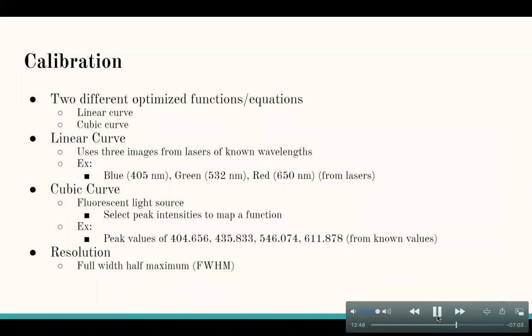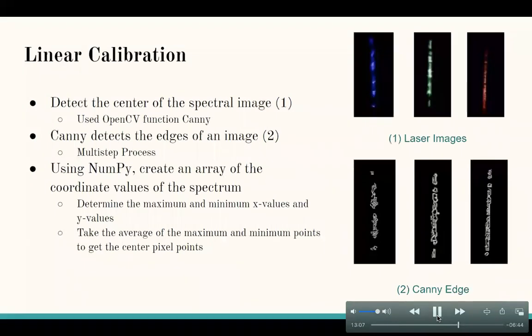The other method is using a fluorescent light as calibration. Based on the peak intensities, we can approximate appropriate X values and wavelength values to find a fit. Along with the laser calibration, the resolution of the design can be estimated using the full width half maximum for each laser. Let's begin with explaining how the linear calibration works.